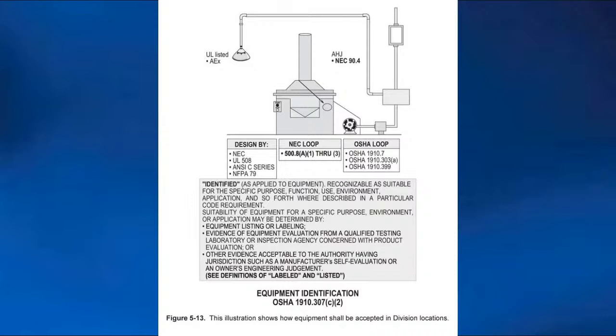For example, in non-incendive, it could either be a listed type installation, or the authority having jurisdiction could go through it and approve it, but most of the time they want a listing, or per 110.3B, they want a NRTL put on it by UL or ETL or someone that the authority having jurisdiction will accept.